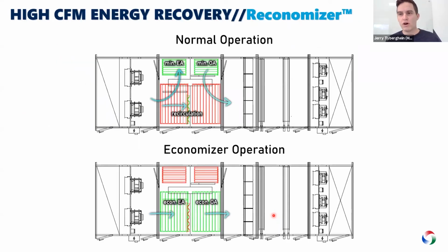And this is actually, I'm wrapping it up here. This is a concept that we are really excited about. It's called the Reconomizer. So I don't know if you've ever run into an issue where you have high CFM on supply, say 30,000, and you only need about 25%, 20% outside air, but you still need energy recovery. Well, if you were to go with the traditional stacked or side-by-side arrangements, you're really hurting on footprint because you have to take that full CFM and split it because you still need economizer.